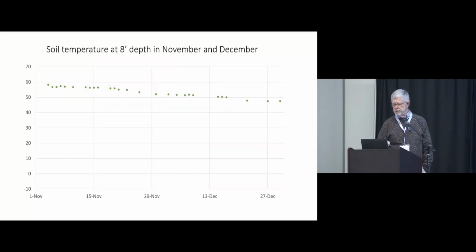This is the temperature at 8 feet that I'm measuring from our greenhouse on our house, which is the midpoint on this 800-foot loop. On milder nights, when the heat doesn't have to run, there can be some equilibration with the ground temperature around the geothermal lines, so I can get an idea of what the ground temperature in general is doing. Over the 2 months I'm showing here, it's dropped about 10 degrees, and it'll continue to drop until it gets down to about 40 degrees later in the winter. So that's just where we're at with that loop.